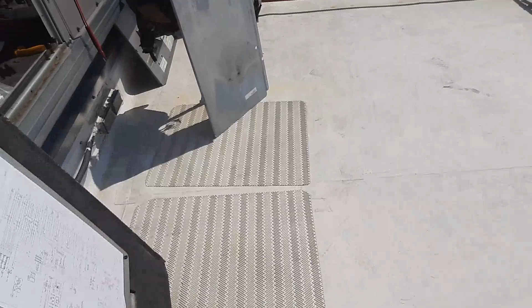But at least I can isolate one other thing. So this is the relay here. I've got the plug pulled that feeds over to it. I've got the transformer disconnected. I pulled these wires that feed over to the fan motors. So I've got the transformer, one of them feeds to the contactor, or the relay. Could be something wrong in that relay too. I need to check that out, and then we should be able to cycle power and see what happens. I pulled everything on that side too, so I'm just isolating, trying to locate where the problem is.